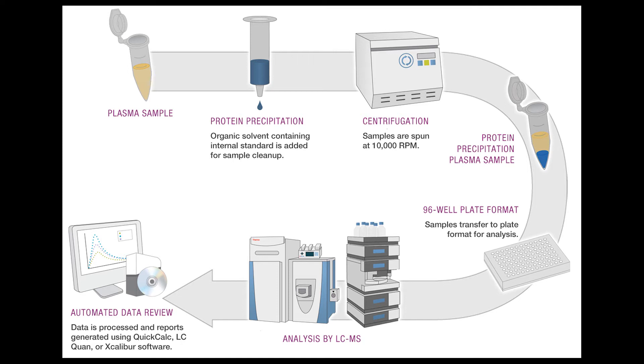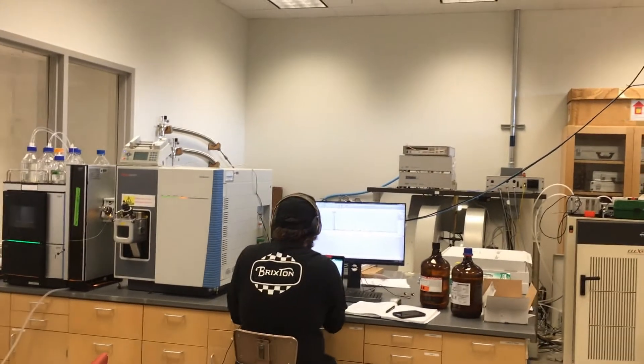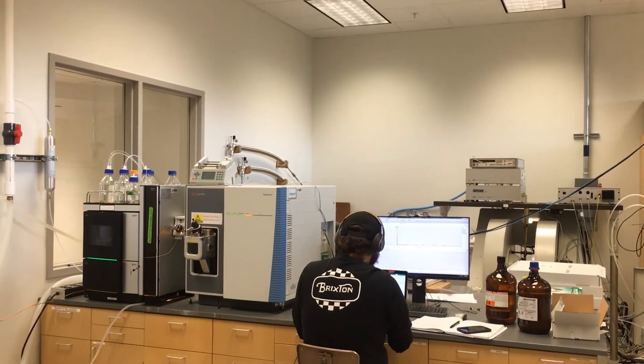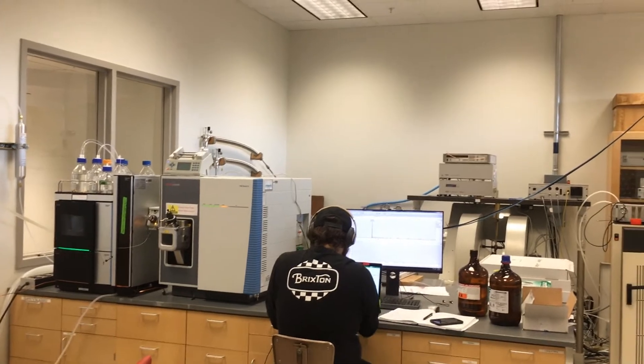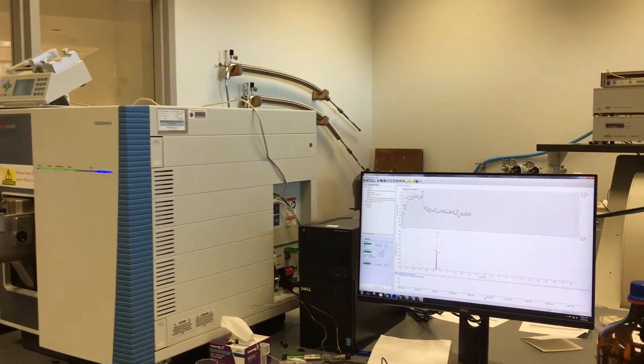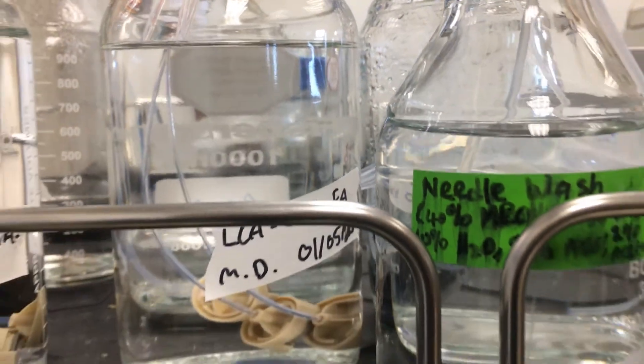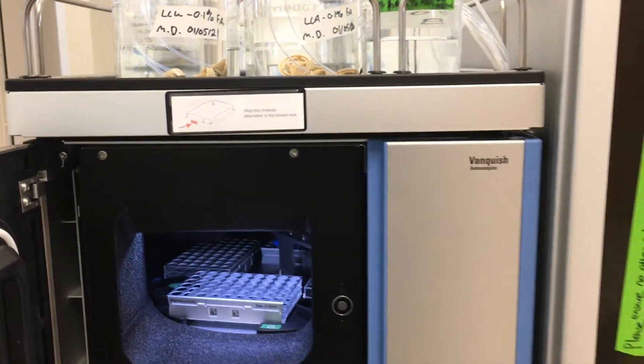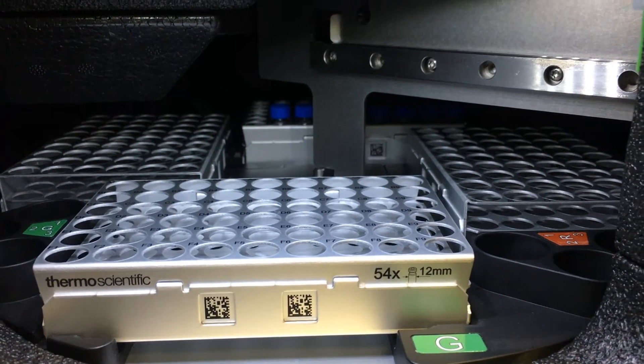The triple quadrupole mass spectrometer from Thermo Fisher, also known as QQQ, is a tandem MS method in which the first and third quadrupoles act as mass filters and the second causes fragmentation of the analyte through interaction with a collision gas. In this case, it is a radio frequency-only quadrupole and can be used in either SIM or scan mode. The method can be used to obtain structural information or for quantitation.